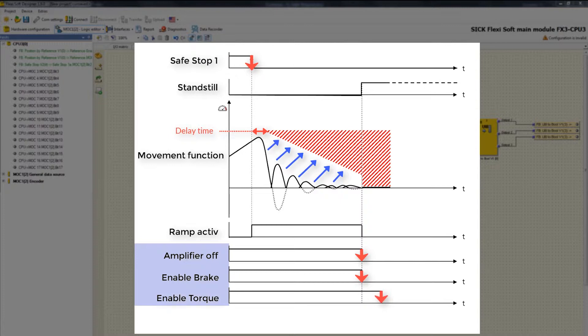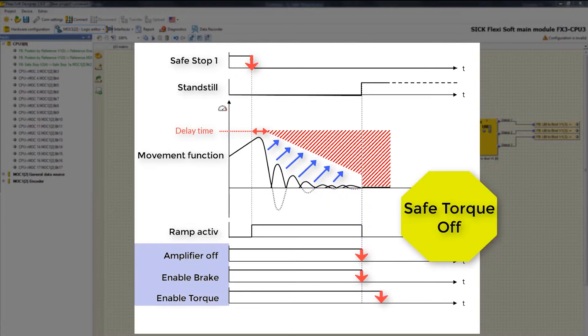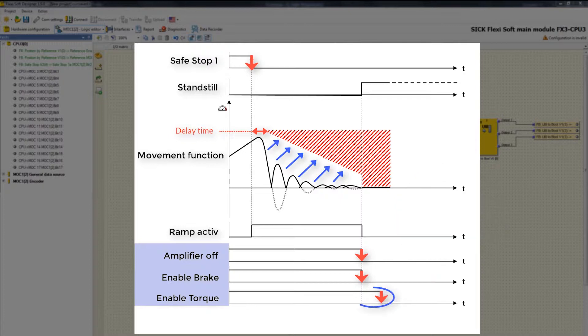After that, the output Enable Torque goes low, and the safety function Safe Torque Off is activated. This function ensures that no torque-generating energy can be applied to an engine. The off delay from Enable Torque is typically set greater than the off delay from Enable Brake, so the torque is cut off only after the brake is closed.